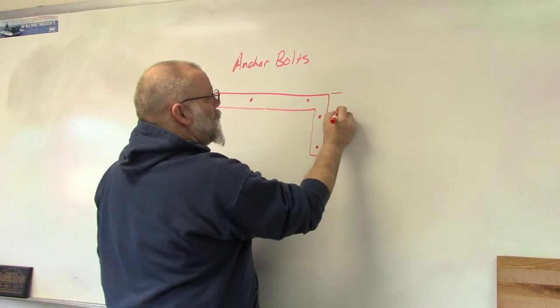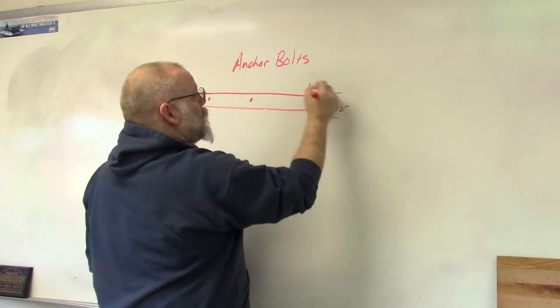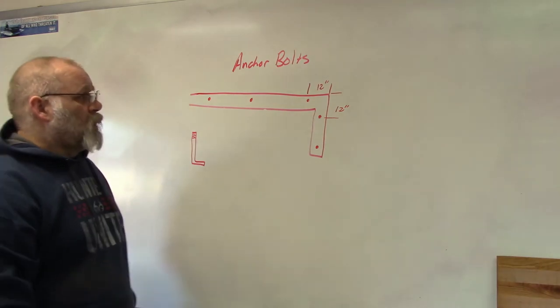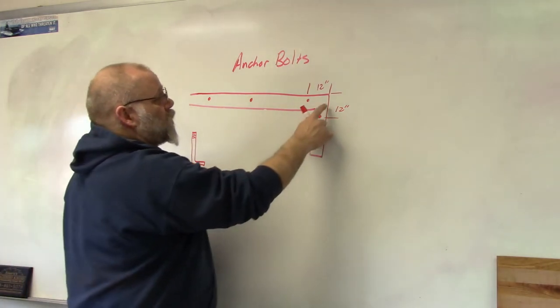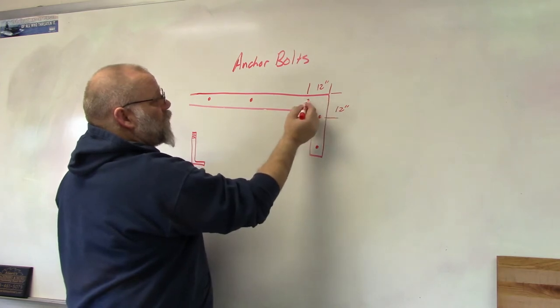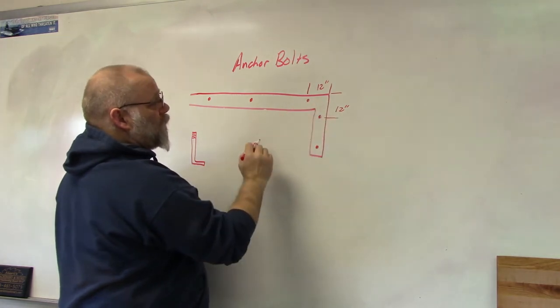Building code says that you need to have an anchor bolt within 12 inches of the corner. So from this corner I measured down 12 inches, I have to have an anchor bolt. And I measure from this corner over, I have to have an anchor bolt.